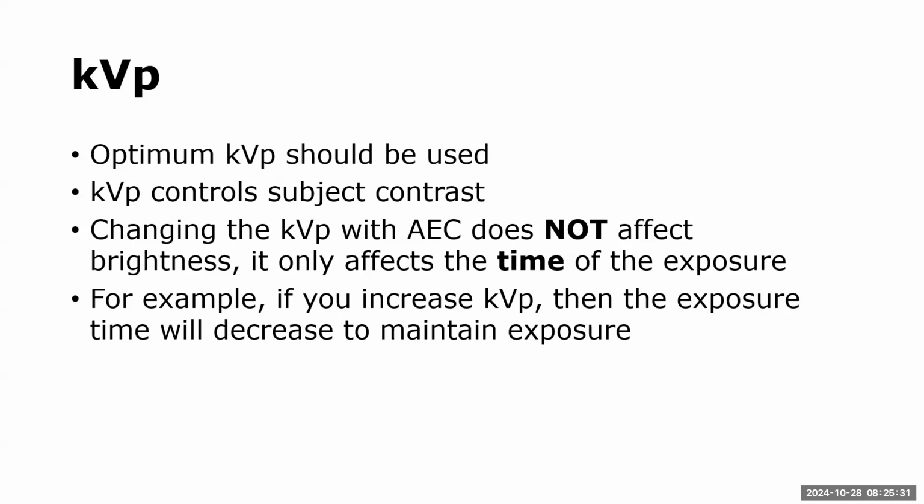Okay. So KVP, we still know that optimum KVP should be used because KVP controls subject contrast, right? We talked about that for the last 2 or 3 weeks. Changing the KVP with AEC does not affect brightness. It only affects the time of the exposure.